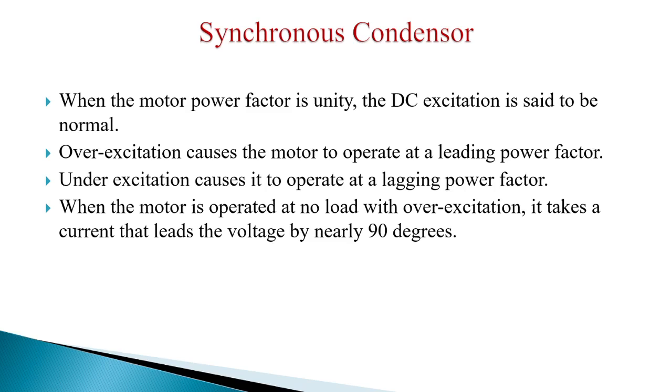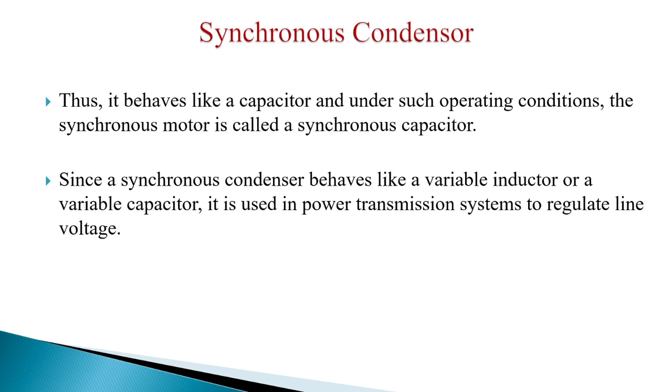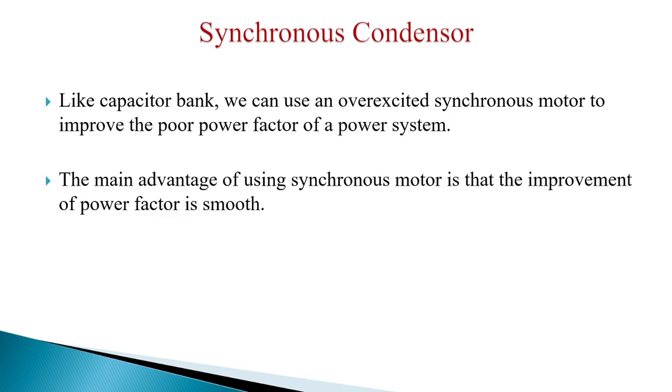When the motor power factor should be unity, the DC excitation should be normal. Overexcitation will cause the motor to operate at leading power factor. Under excitation will cause the motor to operate at lagging power factor. So a synchronous motor behaves like a variable inductor or a variable capacitor. It is used in power transmission systems to regulate line voltage.